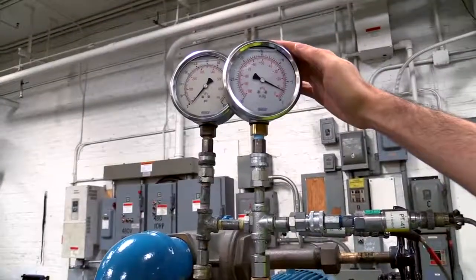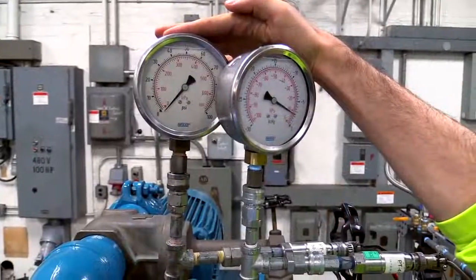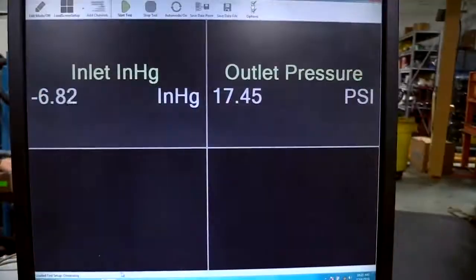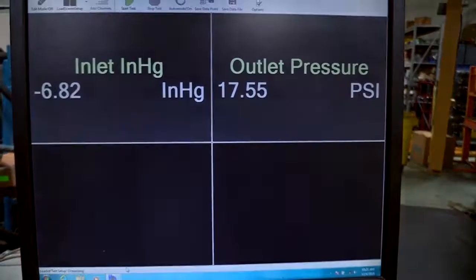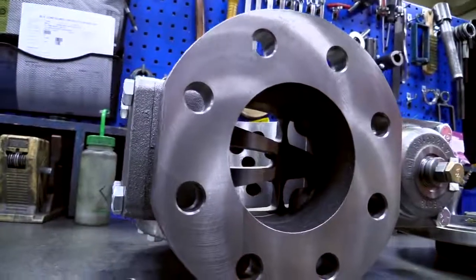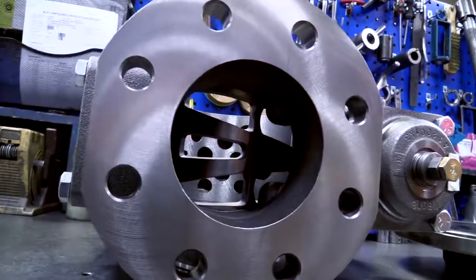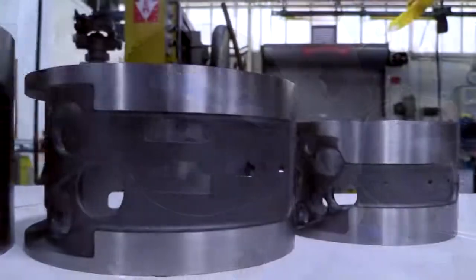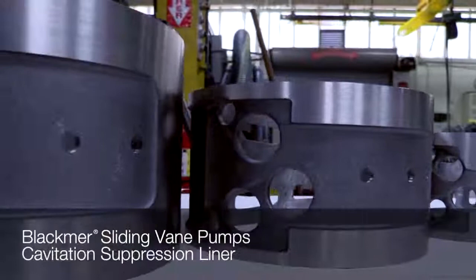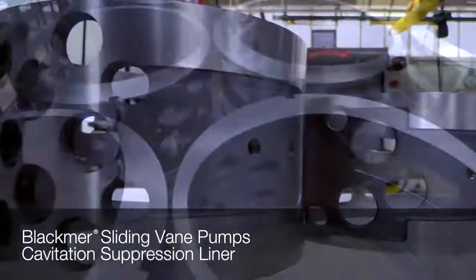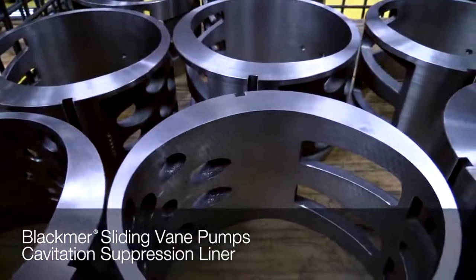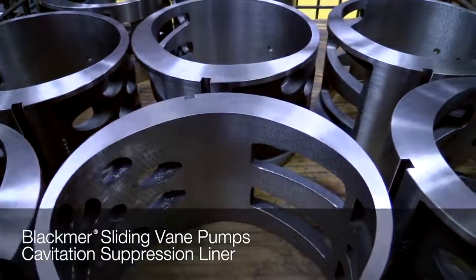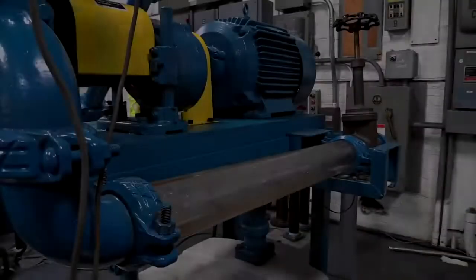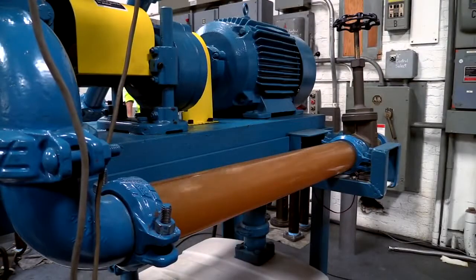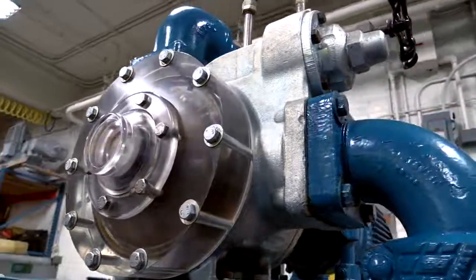All conditions are being carefully controlled and monitored so that we can fairly evaluate multiple pumps under identical settings. Finally, these gauges and valves control the operating conditions, and we can see the inlet and discharge pressure on this monitor. We will be testing pumps with and without this unique device, specific to Blackmer sliding vane pumps. It is a cavitation suppression liner and is designed to mitigate the negative effects of cavitation. We'll come back to this in a moment. First, let's run this Blackmer LGL3 sliding vane pump without a cavitation suppression liner.